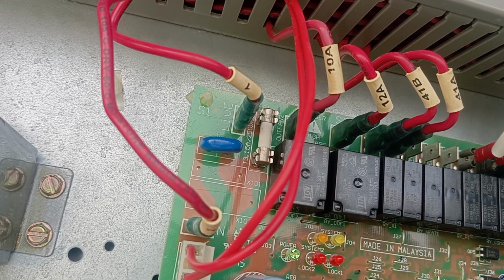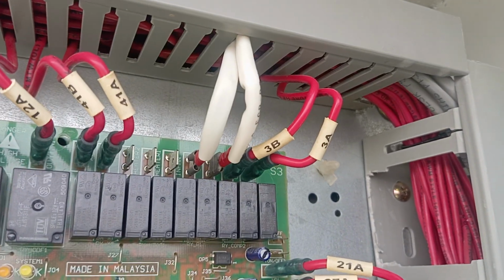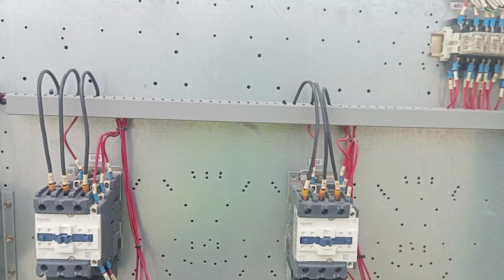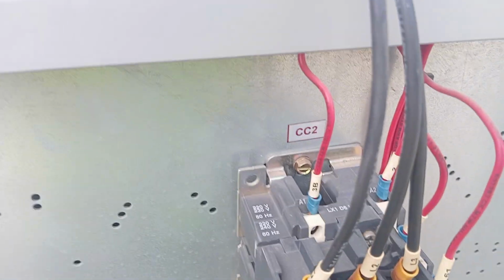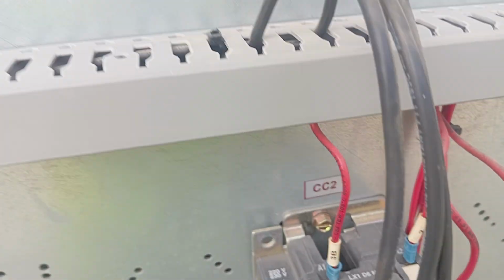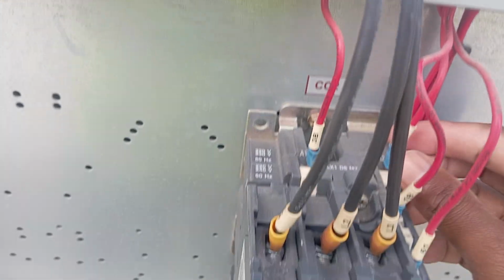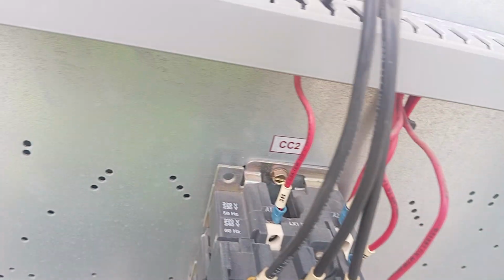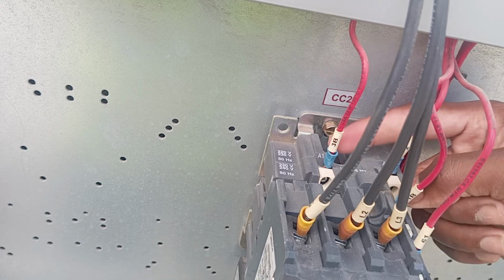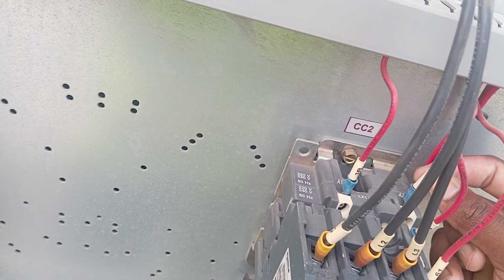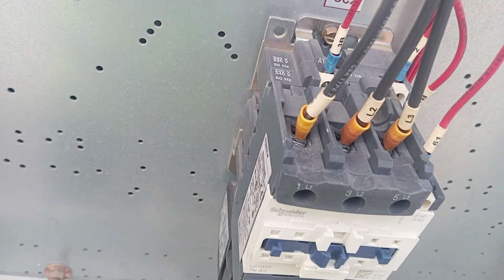contactor coil voltage. So you see these first cables 3A and 3B come directly to the contactor coil voltage. So I will show you. As I said before, 3B, you see there coil voltage 3B. Then I saw here a number 2 cable. It is the neutral cable to start this contactor. It is neutral and 3B. 3B is the phase and this is neutral. With 220 voltage the contactor will start.